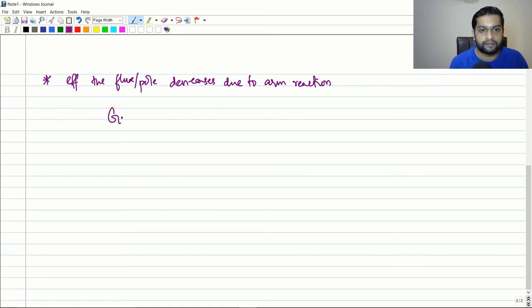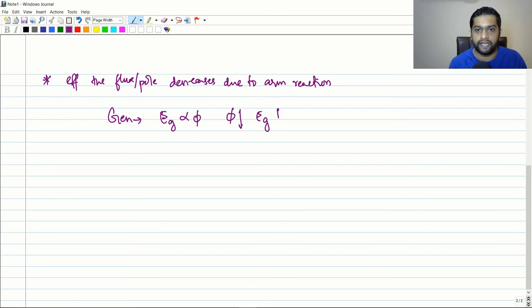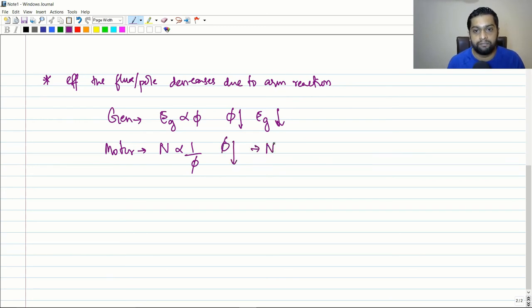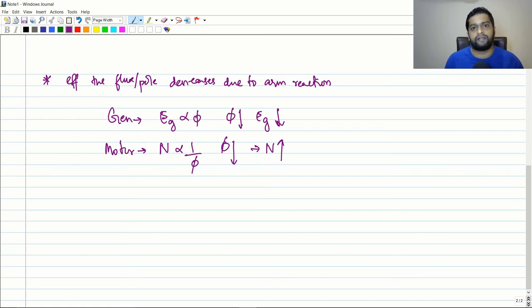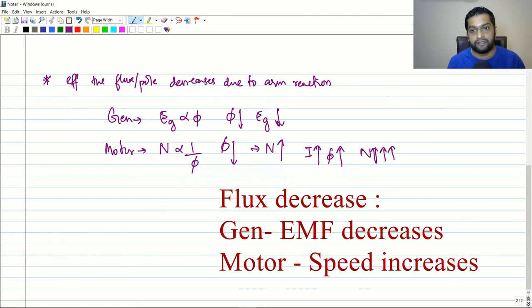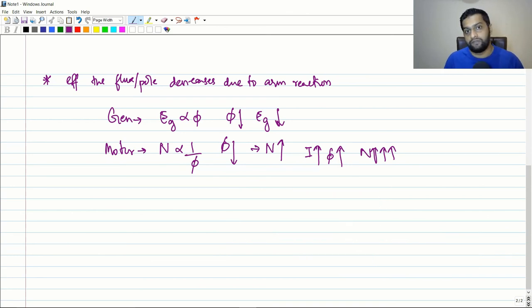In a generator, the EMF generated is a function of flux, so if the flux decreases, the generated EMF decreases. When we discuss motors, you will see that the speed is inversely proportional to flux — so if flux decreases, speed increases above its rated value. As speed increases, the motor tends to draw more current, which causes more armature reaction, which further reduces flux, which further increases speed. In some DC motors this leads to a dangerous runaway condition.